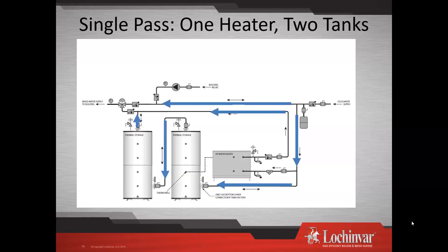Ultimately, two storage tanks in series is the same idea as one really tall tank. Hydraulically it would be very similar. You'll get your stratification. The purpose of that is, let's say your system is drawing in water at a faster pace than the water being pulled into the heat pump. Heat pumps, if it's got a high delta, it's got a fixed output, it's going to have a low flow rate.